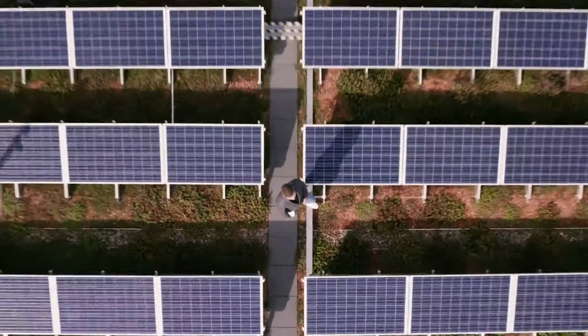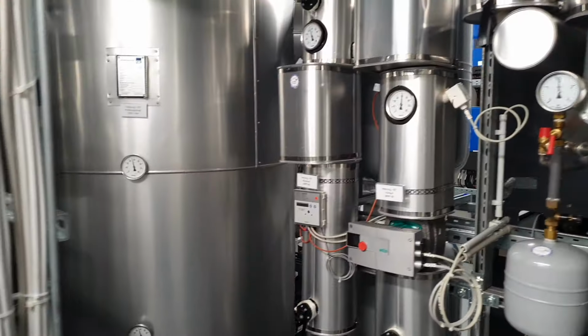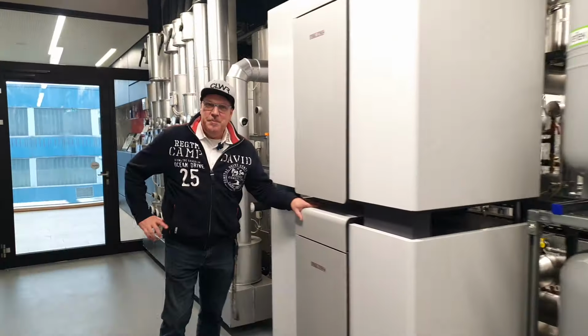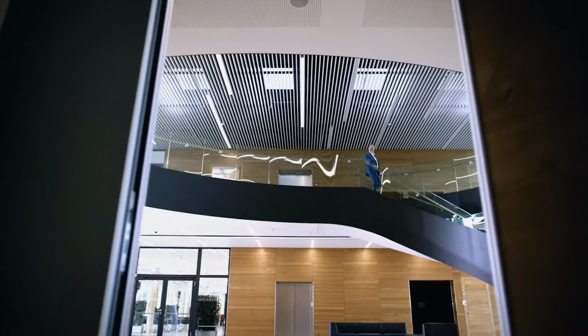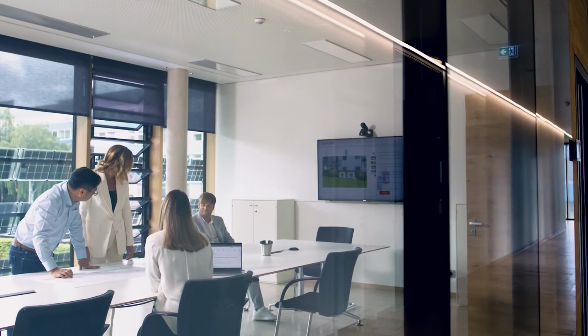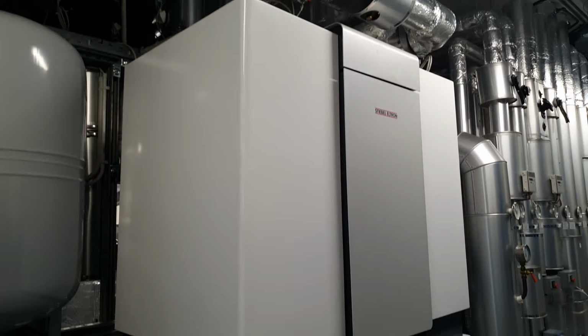The panels on the facade with solar trackers, paired with the photovoltaic field on the roof, create a 120 kilowatt photovoltaic system that powers 2 cascading geothermal heat pumps, which utilize groundwater to accommodate a heating demand of nearly 150 kilowatts and around 90 kilowatts for summer cooling, for more than 3,000 square meters of offices and practice rooms.